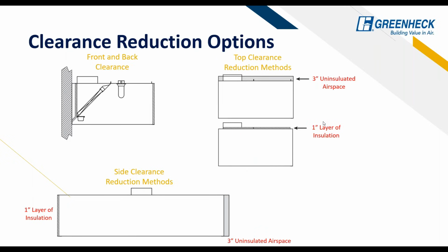Okay, and then some more clearance options, as I said. So typically, you'll get the 3-inch uninsulated airspace on the back of the hoods. We can also add a 1-inch layer of insulation on all sides to get some zero clearance options. So if you are looking at a wood structure or something like that, an old space where you can't redo that with a metal stud or anything like that, then we do have some zero clearance options that you can look at as well.